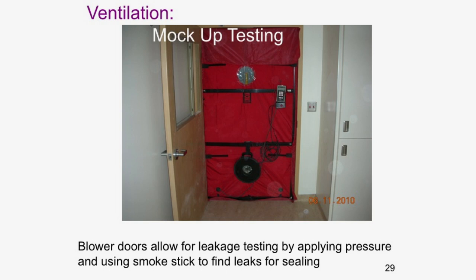One of the things we tried to do in our new old hospital, slide 29, is leak test. A common consideration for leak testing and energy management is to seal a building, homes primarily. That's really a good thing if you can do it, because it will help control the ventilation to minimize the leakage. That leakage deals with pressure, and buildings become pressurized. If we don't have a good seal on the building, we don't have the control we want for our special ventilation rooms, especially if the building goes negative and starts sucking moisture into a highly treated air environment.